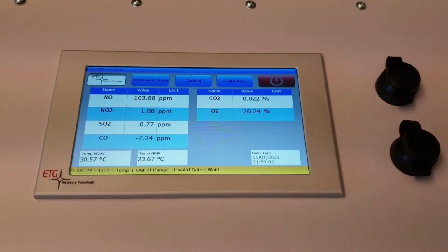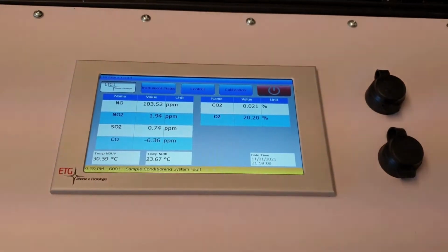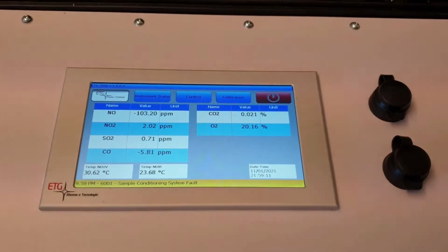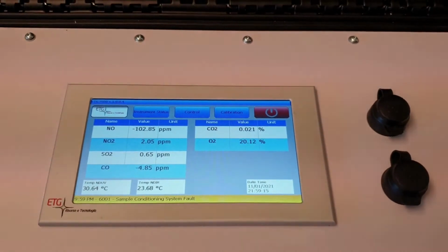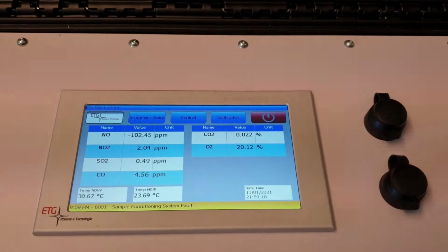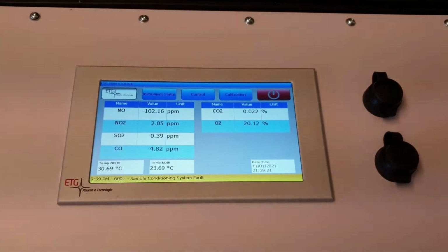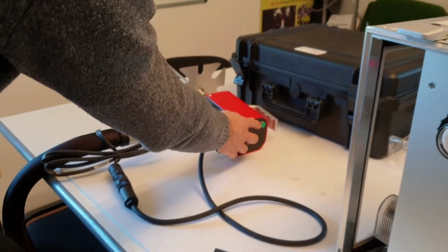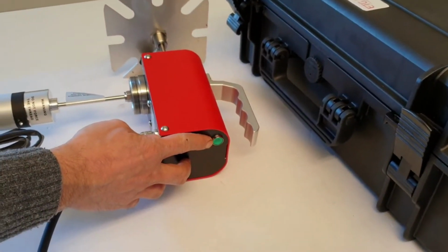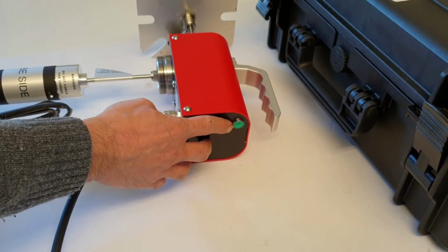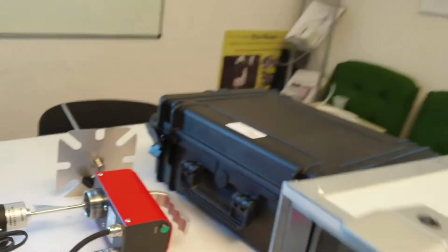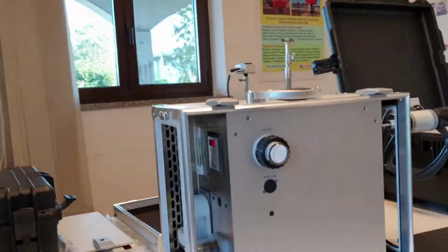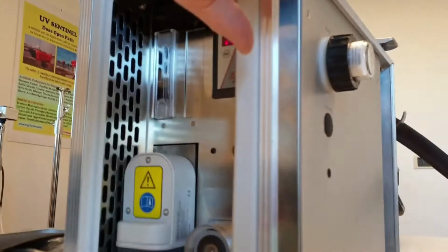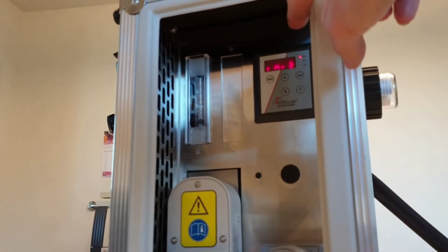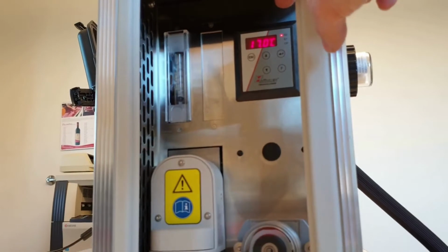The analyzer is on alarm because the NDUV and NDIR sensors have not yet reached the temperature, and also the sample conditioning system is on alarm because it has not yet reached the temperature. As you can see on the probe there is a LED. When it becomes green, it means the probe is on temperature. And also on the display of the sample conditioning unit you can see when the system has reached the set temperature.